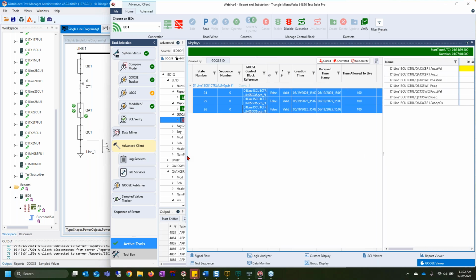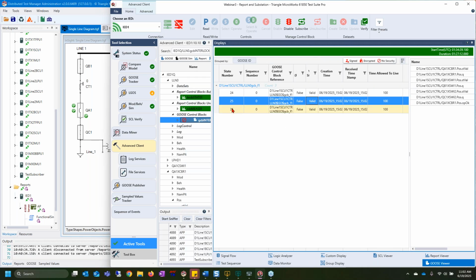Now, importantly, what you might notice is that we're not getting one on every single retrans. Even as we approach that Tmax here, we're not getting state number 26, 26, 26, 26, right? Because that would just fill up this whole display and make it harder to find the data that you want. So we'll only see the state number as it's increasing in here. Now, the retrans are used for the GOOSE tracker in order to make sure that we are still connected and we haven't had any sort of disconnection or a stream disappearing. So after we do that, we can see the values and update our model based on that.